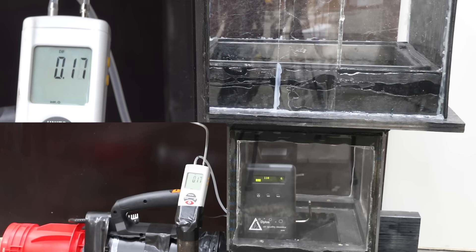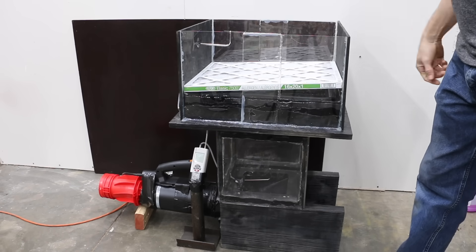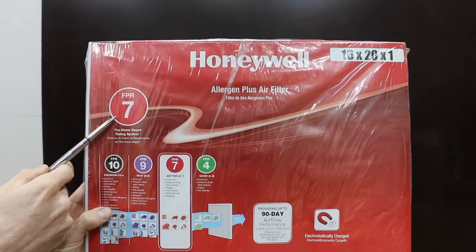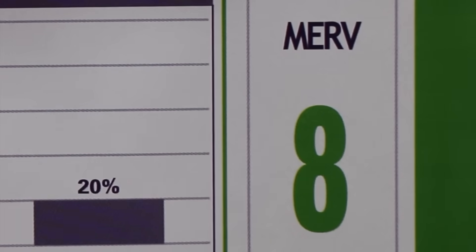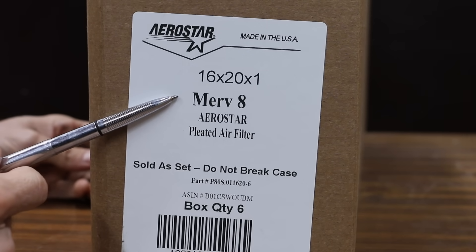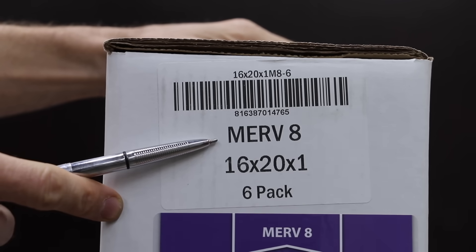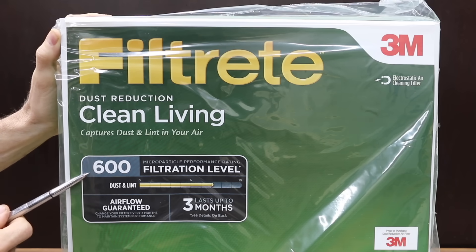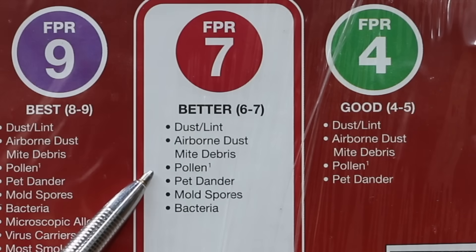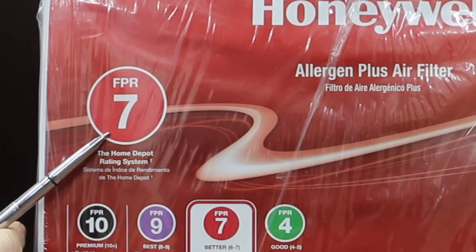So there's very little stress on the blower motor since air is moving freely. Before we begin testing the filters, a little more information on how filters are rated. Different brands use different rating systems, which can cause a lot of confusion — FPR, MPR, and MERV are the three rating systems. MERV is the domestic and international industry standard established by the American Society of Heating, Refrigerating, and Air Conditioning Engineers. MPR stands for Microparticle Performance and is used by 3M. FPR stands for Filter Performance Rating and was created by Home Depot. All three rating systems can be cross-referenced for every filter.